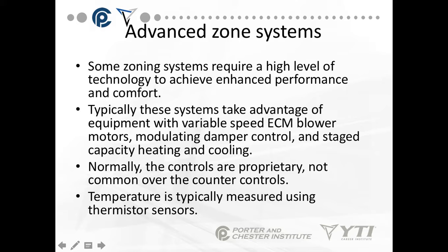Then we have advanced zoning. Some zoning systems require a high level of technology to achieve enhanced performance and comfort. Typically, these systems take advantage of equipment with variable-speed blower motors, modulating damper control, and staged capacity heating and cooling. Normally, the controls are proprietary — they're not common over-the-counter controls. The temperature is typically measured using thermistor sensors.